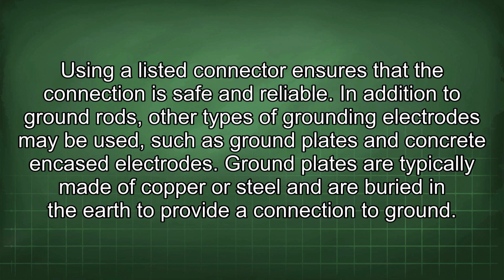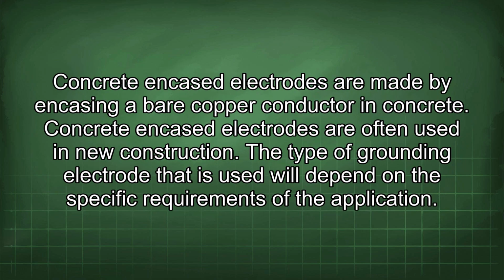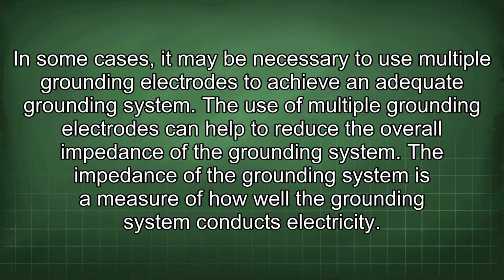In addition to ground rods, other types of grounding electrodes may be used, such as ground plates and concrete encased electrodes. Ground plates are typically made of copper or steel and are buried in the earth to provide a connection to ground. Concrete encased electrodes are made by encasing a bare copper conductor in concrete. Concrete encased electrodes are often used in new construction. The type of grounding electrode that is used will depend on the specific requirements of the application. In some cases, it may be necessary to use multiple grounding electrodes to achieve an adequate grounding system.